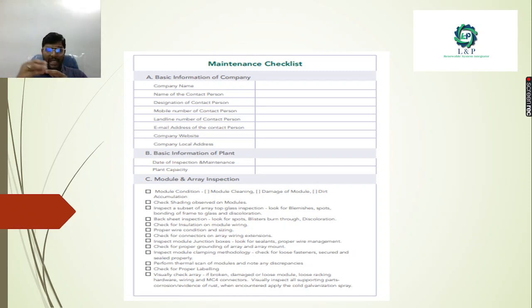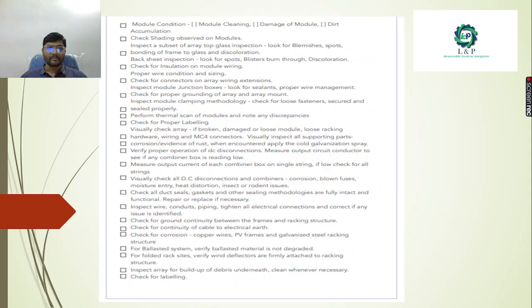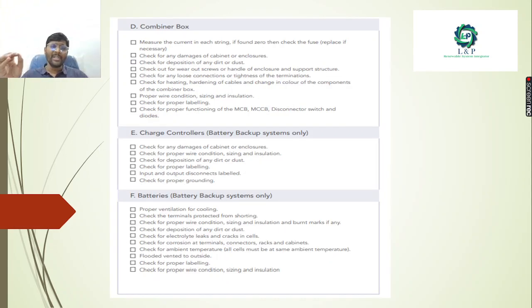Check that the connectors have been connected properly, and make sure the labeling is proper. Is there any new shading over it? Make sure your AC side and DC side fuses are correct. Make sure your surge protection devices are okay, and make sure your batteries are in a properly ventilated room. If they are sulfated, please clean them. Make sure there is enough distilled water in the batteries.